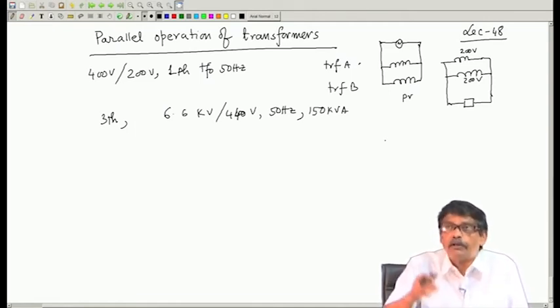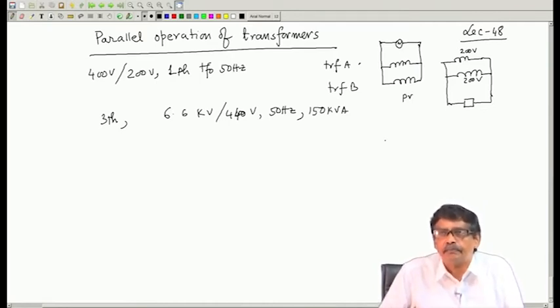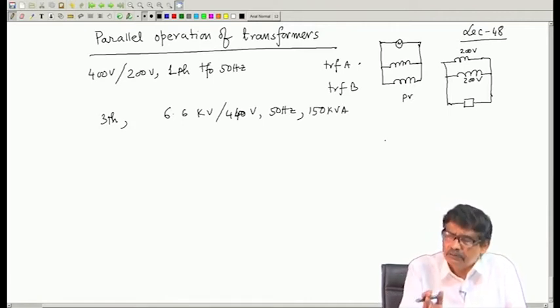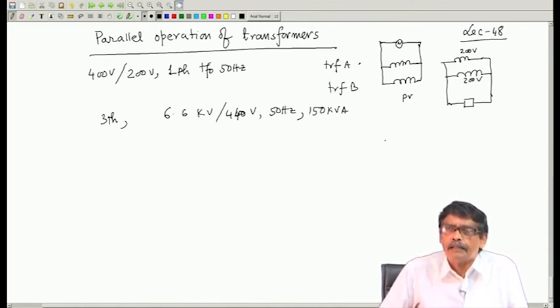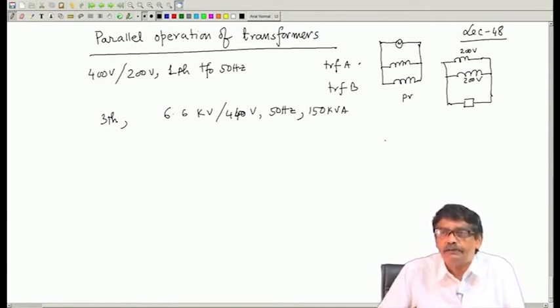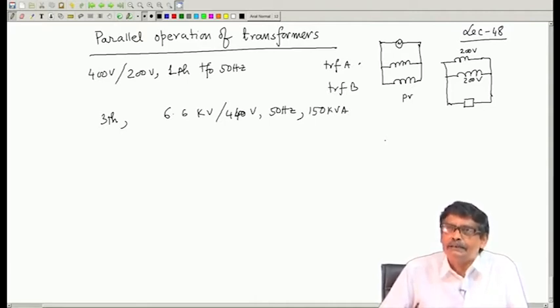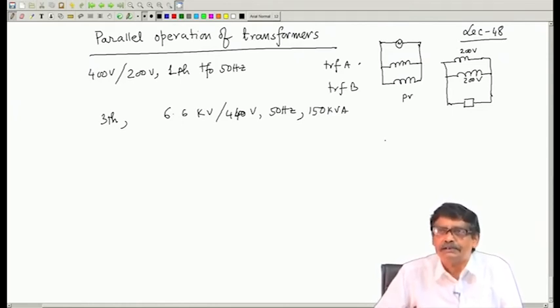But had there been two transformers operating in parallel, it is very unlikely that both of them have simultaneously become faulty or need servicing. Therefore, if two or more transformers are connected in parallel catering a certain amount of load, it is likely that one transformer will become faulty. Why would all of them suddenly become faulty? So, one of them becomes faulty, you take it out. Then the kVA you can supply will be less, no doubt, by one transformer's rating, but nonetheless some of the consumers may be supplied power. That is no mean thing.